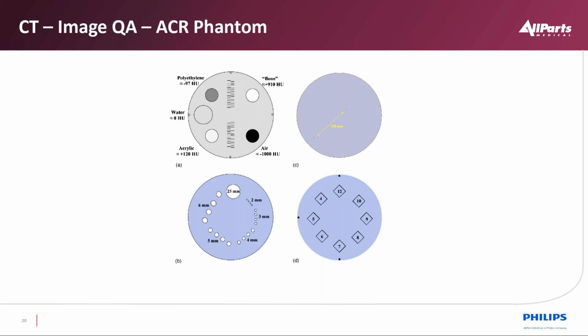Then we have pins, as you can see down at the bottom, that represent different items in a soft tissue window range. That could tell us whether our low contrast detectability is good. That's a small change in CT numbers. There's only about a 6% difference between these, though you can see it on the screen here. It's much harder to see actually when the phantom's reconstructed. And then obviously we have different line pairs represented by the numbers you see there.